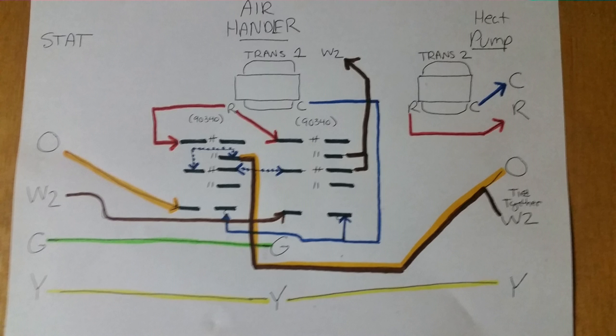W2 travels along the orange and brown path to the relay. But since the O relay is not energized, that jumper, it passes across through the normally closed terminals across to the other relay following the blue dotted line across those normally closed terminals and onto W2 to energize the heat strips.